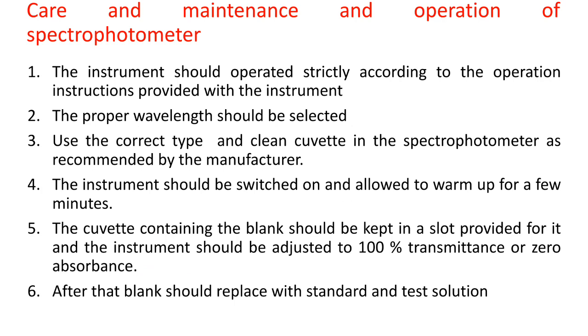The instrument should be operated strictly according to the operation instructions provided with the instrument, and the proper wavelength should be selected based on whether the solution is colored or colorless. Use the correct type of clean cuvette in the spectrophotometer as recommended by the manufacturer, and the instrument should be switched on and allowed to warm up for a few minutes.